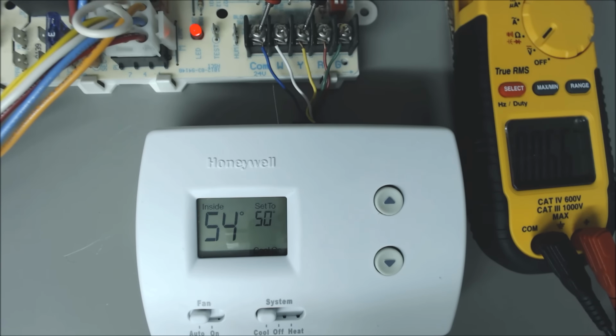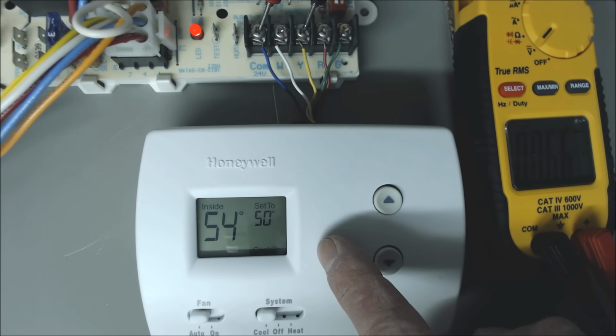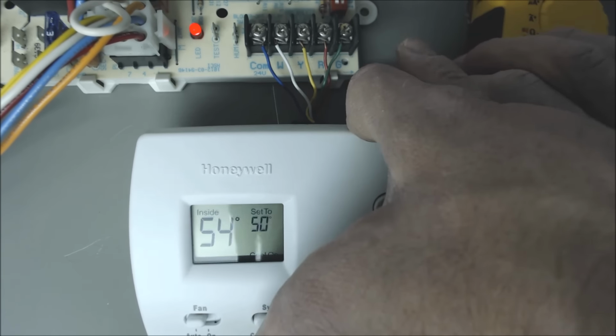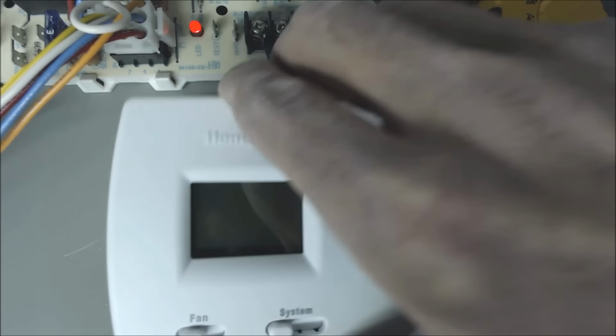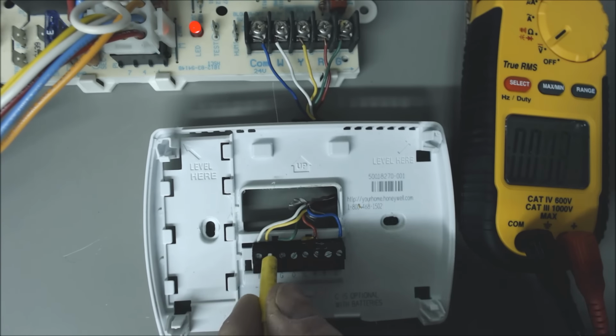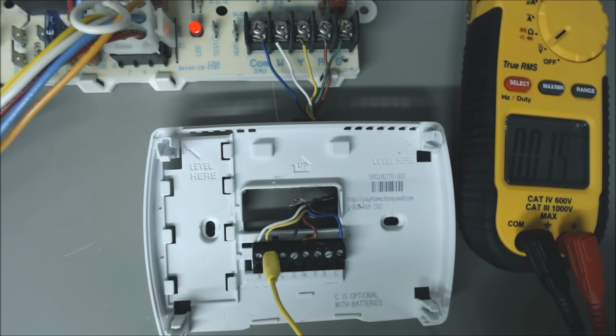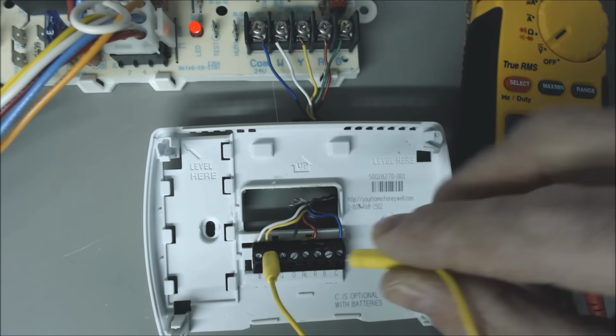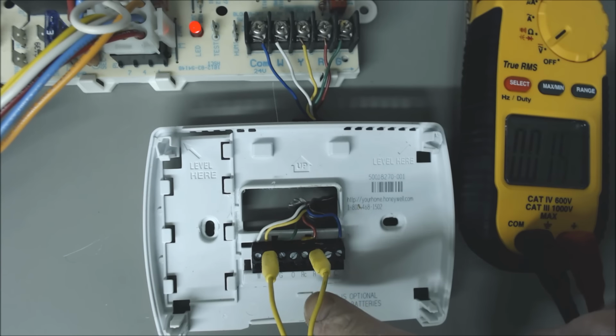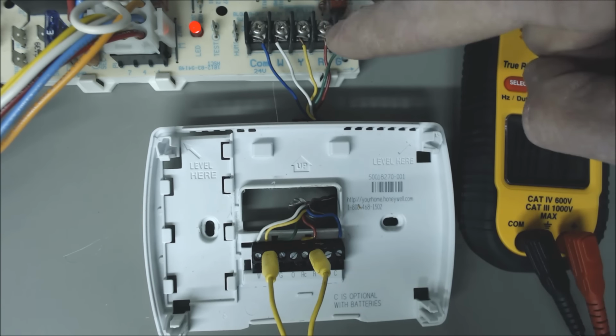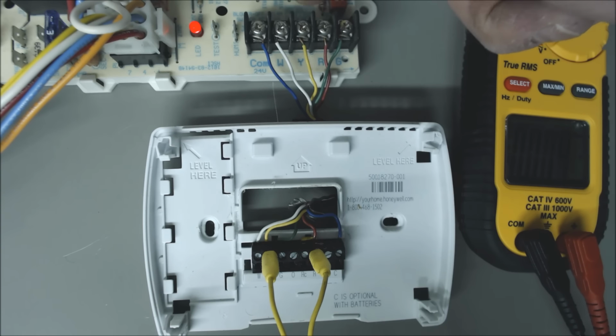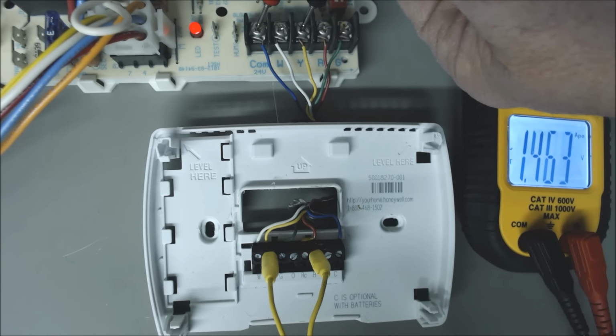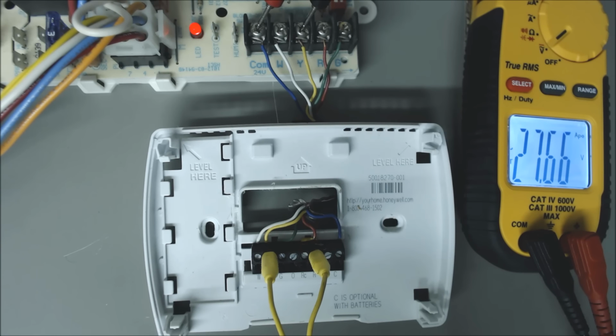So in our case, we're just going to pull the face off, and we're just going to jump it out. But normally you're just going to wait for the 5-minute delay because you want to actually check to make sure this thermostat face is working properly. So we jumped from R to Y, and now we should be having a 24 volt signal on the control board telling basically the blower motor to turn on in high speed. Now we're going to read our voltage from Y to C, and you see that we are reading 27.6 volts. So that is working properly.